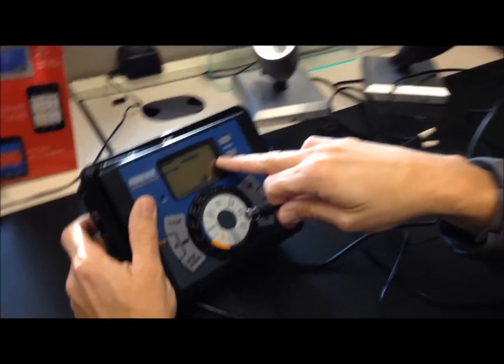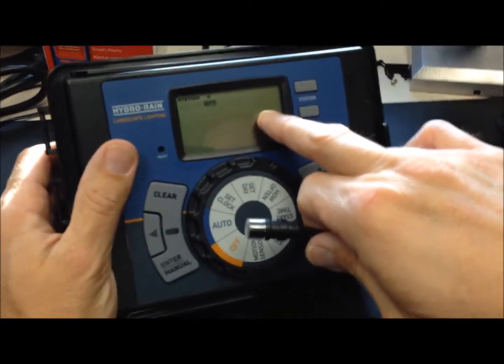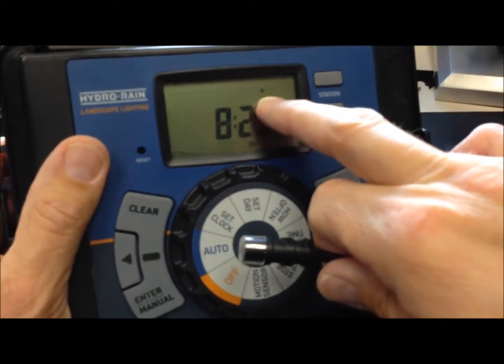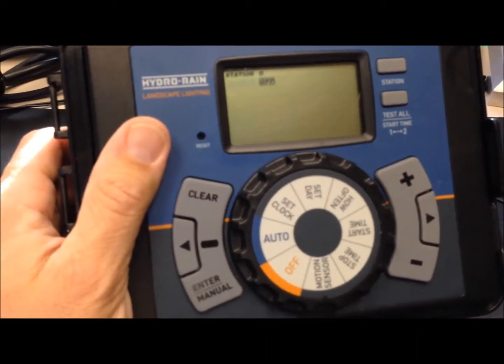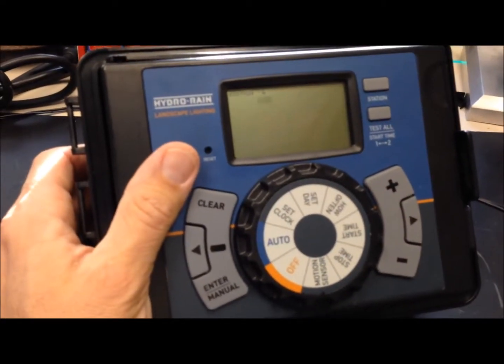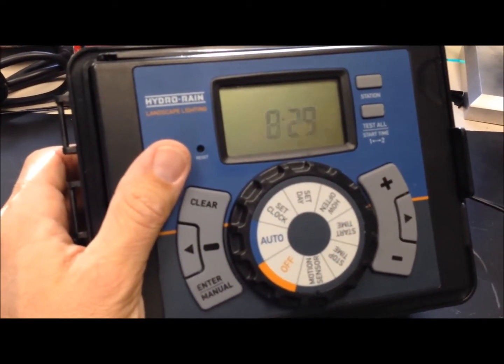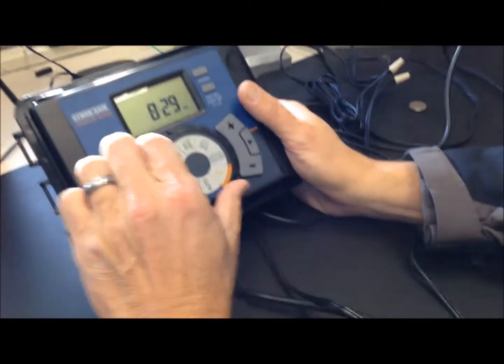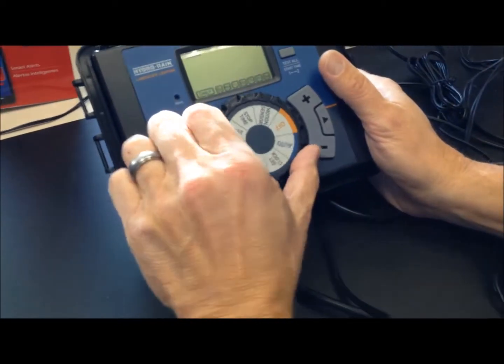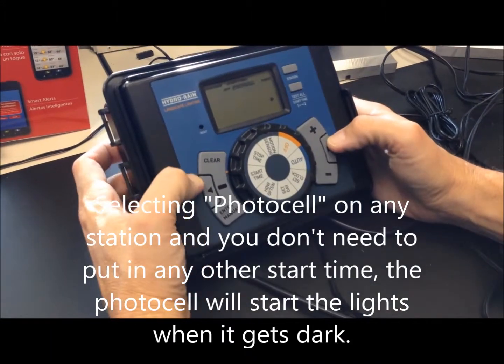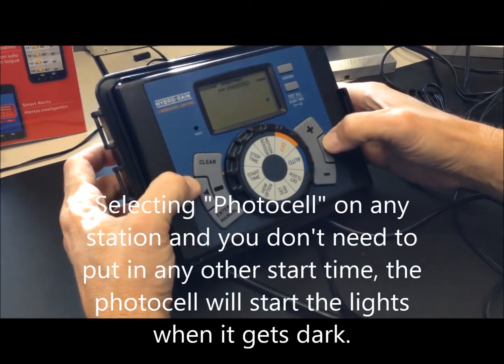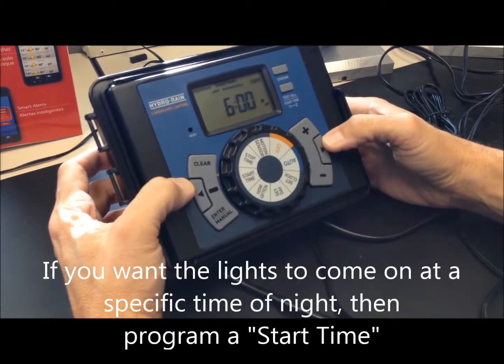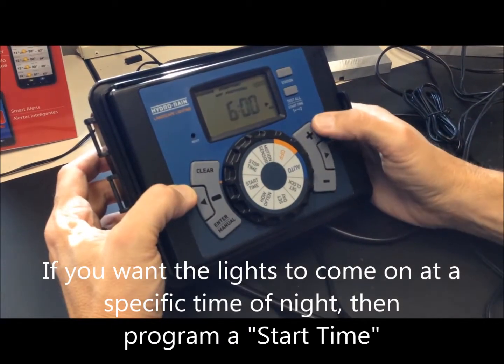Notice we're showing here, while in auto mode, we show a sun symbol, which means it's detecting light. When it goes dark, it will show a moon. Back to programming. When you set your start time, you can choose the photocell, which means you don't have to set any times at all, at least for the start time. Or you can go timed. If I go timed, it does not use the photocell.